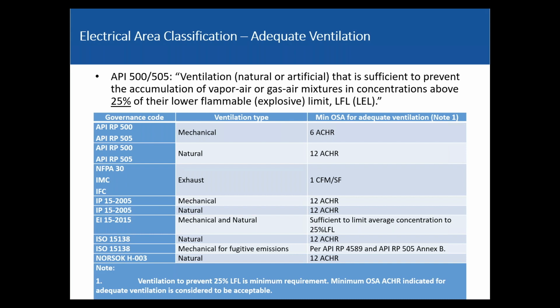But they all have a little guidance note. The guidance note said you can consider having adequate ventilation if you do 6 air changes an hour, but you don't really know it. Then there's another method where you look at what your gas sources are, what the emission is, and you can look at it from an analysis standpoint: I really need this many air changes an hour. And I'll say in the oil and gas world, everybody talks about air changes an hour, not CFM per square foot. It's a little bit different. Like it or not, that is what everyone talks about.